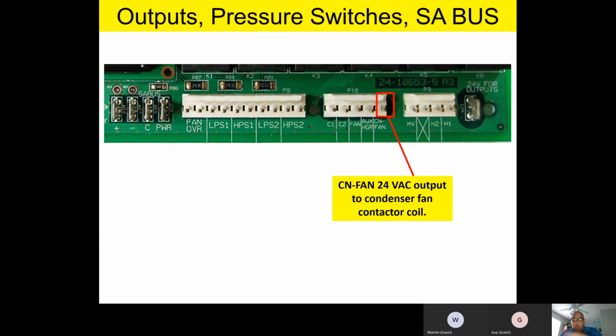So once all permissions are met, in other words, the switches are closed and we've got a thermostat call for operation, the board will then output 24 volts on that pin to bring the condenser fan on for cooling operation, or if it's a heat pump, it'll bring the condenser fan on for heating operation as well. Here we have an auxiliary heat 24-volt output for hot gas reheat. So if your unit is equipped with a hot gas reheat solenoid, this is what energizes the hot gas reheat solenoid if it's so equipped.